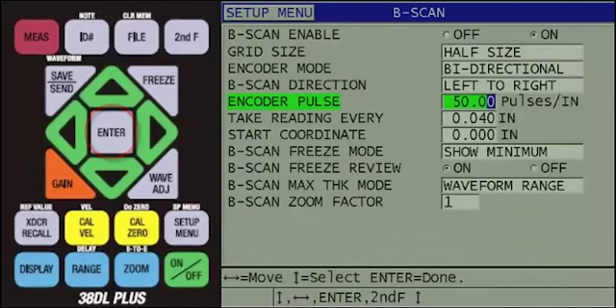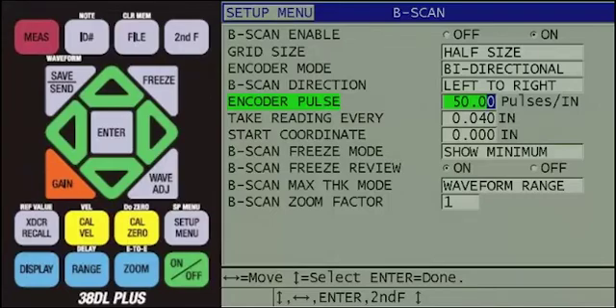Since we are using the Olympus B-Scan-ENC buggy, we will use the default encoder pulse of 50 pulses per inch, or if you are using metric units, it would be 1.97 pulses per millimeter.